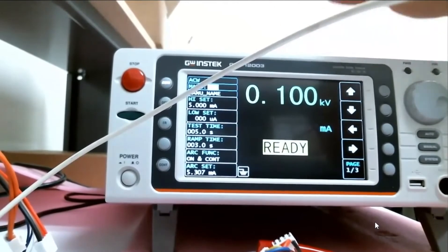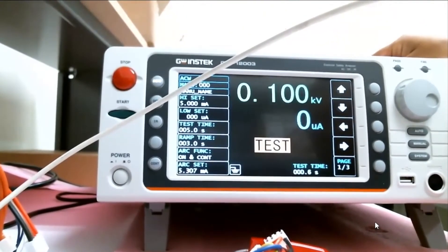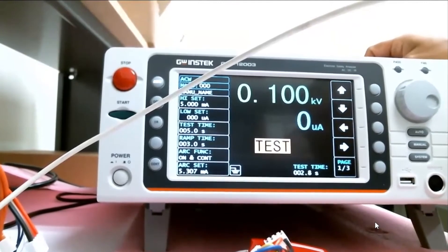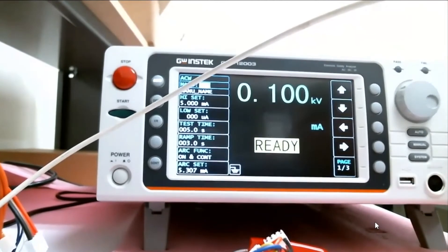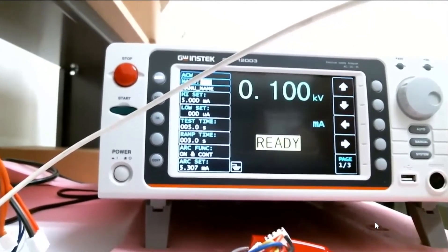So this test is ready to go. I would press the start. As you can see, it's ramping up to the voltage, and once it reaches 100, it tests for 5 seconds and keeps testing. So typically tests in the real world run for about 30 seconds to a minute, obviously with higher voltages.